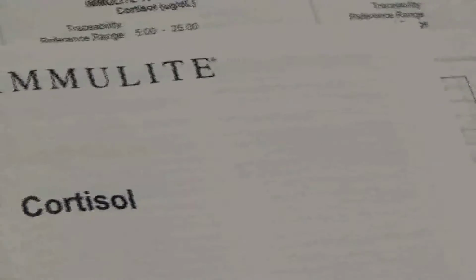The process works whereby once we've added in our serum, which is told to us based on a manual for each hormone value, here showing cortisol, exactly how much serum is required at the minimal amount to run one test sample. It's going to grab a serum sample, and then place it into a tube along with the specific components for cortisol, so that it binds the cortisol within that serum sample to a coated bead within the test tube. It can then flush away anything else that is not cortisol based, and we'll be able to get an actual measurement of cortisol only.